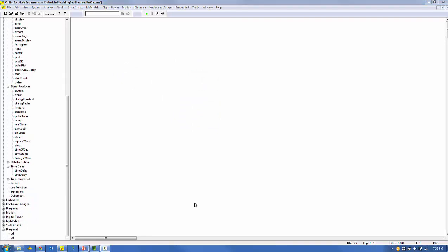Most digital controllers execute at 1 or more fixed update times. It is good practice to create a unit delay compound block whose update time can be controlled by a single global variable. We'll name our unit delay compound block UD. It will consist of a unit delay triggered by a pulse train with the time between samples set by a global variable named update time 1.